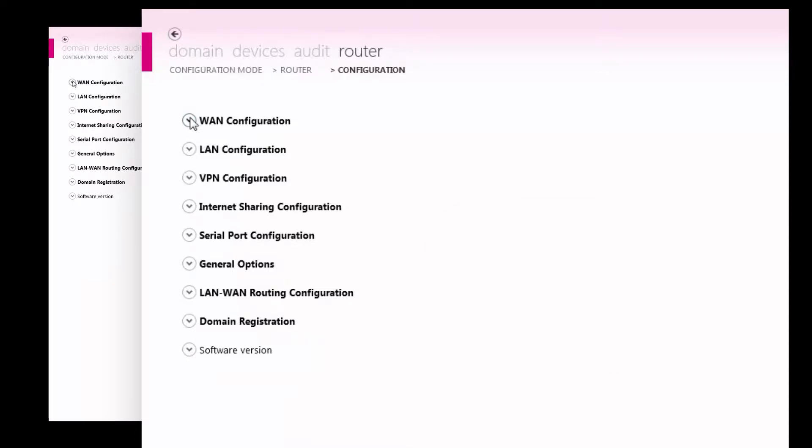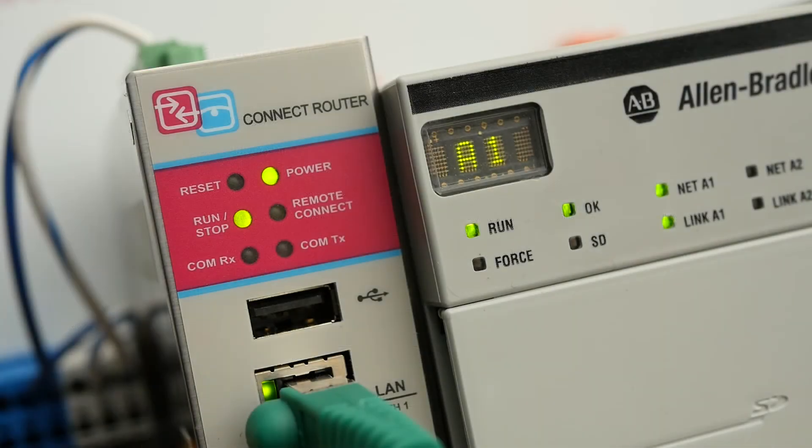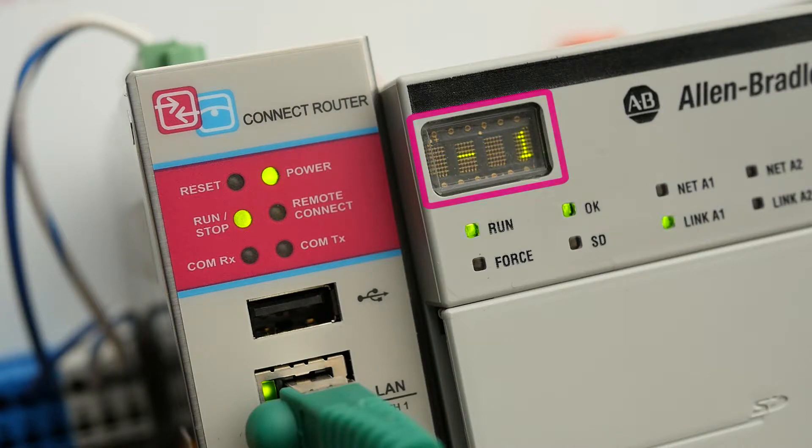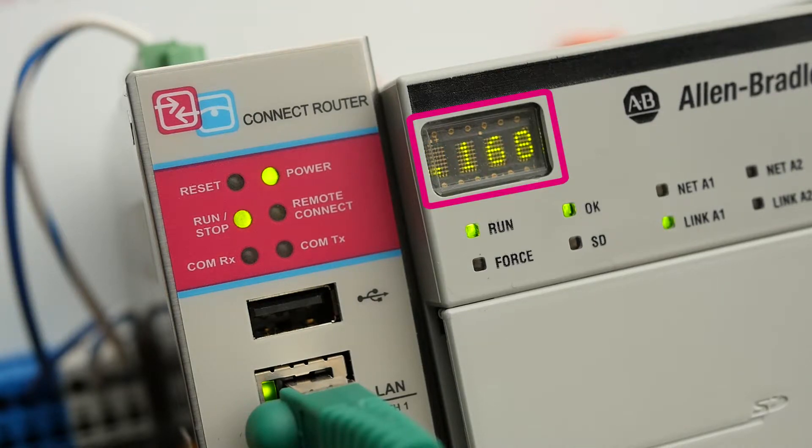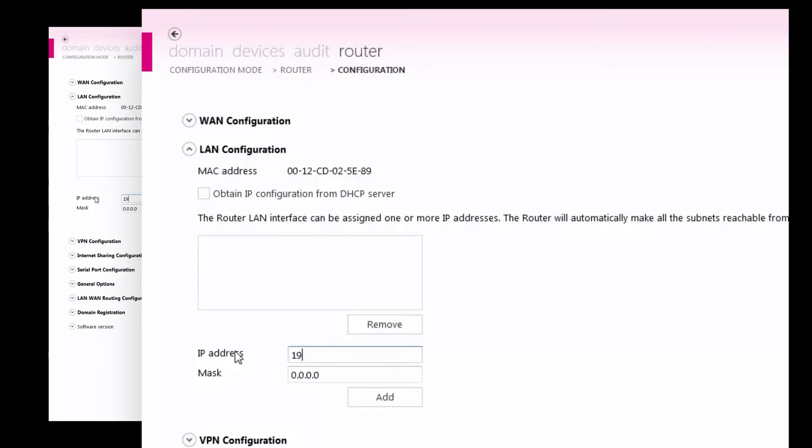Next, the LAN port of the router must be assigned an IP address on the PLC network. My CompactLogix PLC has the IP address 192.168.0.5. I will assign the IP address of my router to be 192.168.0.1.